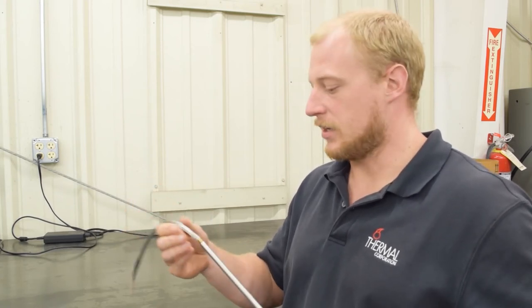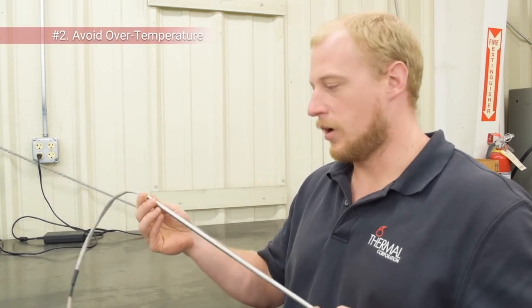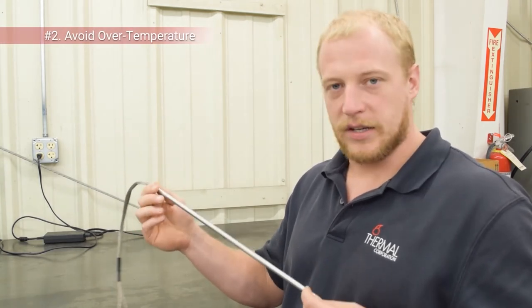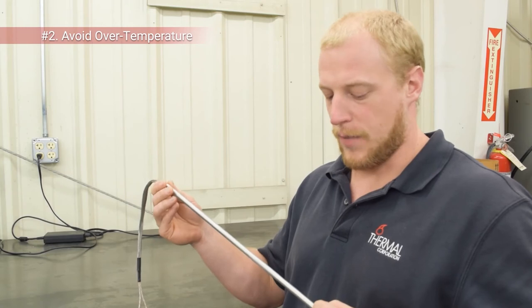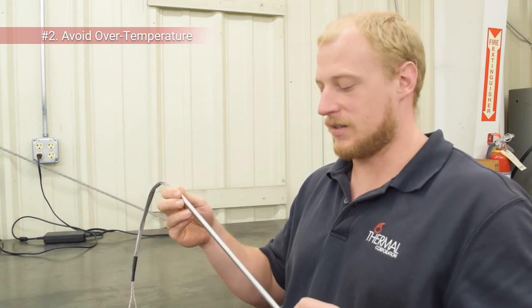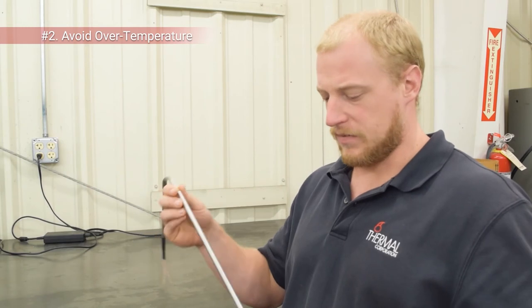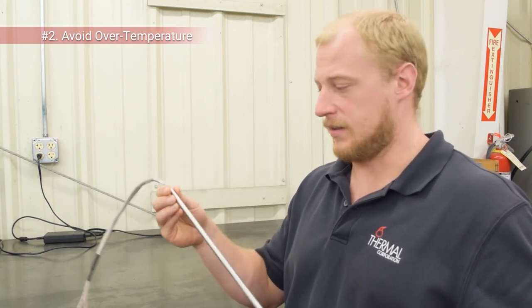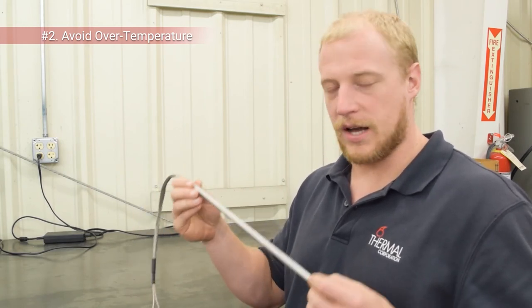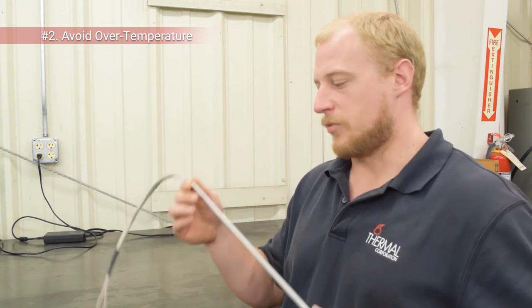The second thing is you want to avoid over-temperature. You want this to fit snugly in your mold or bore. Ideally you just have a couple thousandths around the heater as your gap. If this is loose in the hole, the heater is going to get really hot and burn out really fast. So make sure it's a good fit.